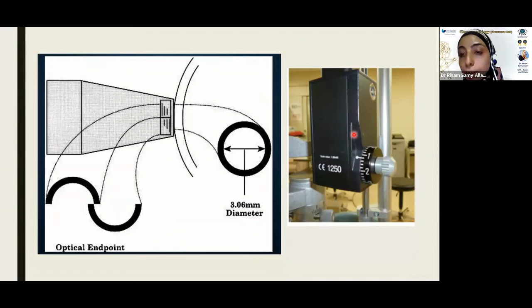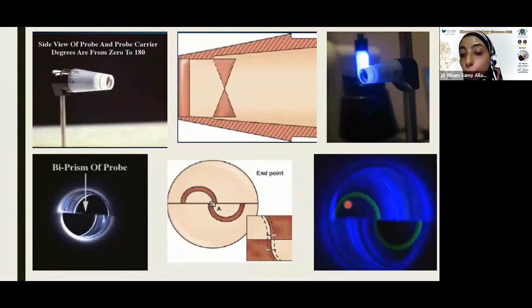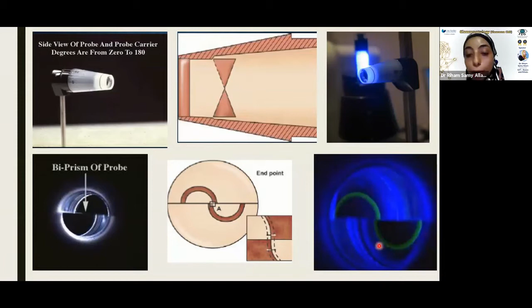Okay. Then, as we said, this is the probe of the applanation, and it is mounted on a slit lamp, and we will find the endpoint by having these two circles. Again, we have another confounder, which is the tear meniscus around the tip of the applanation itself. So to differentiate these two menisci, we have to stain the tear meniscus in order to have a clear-cut endpoint, which is done by using the cobalt blue filter in addition to fluorescein. And so we will have clearly demarcated yellow marks that fluoresce with the cobalt blue and can get a near estimate of the intraocular pressure.